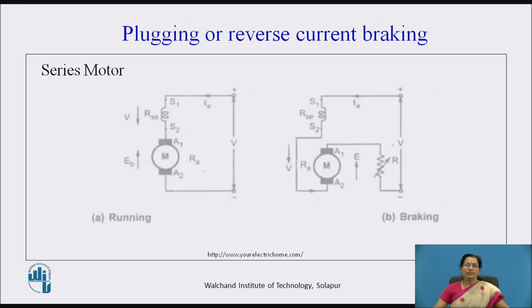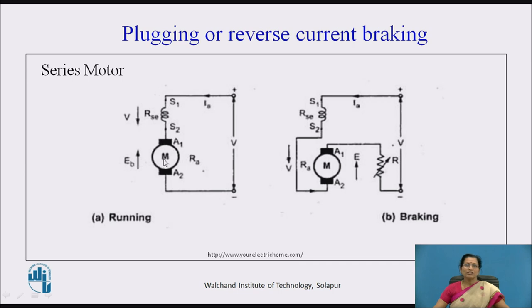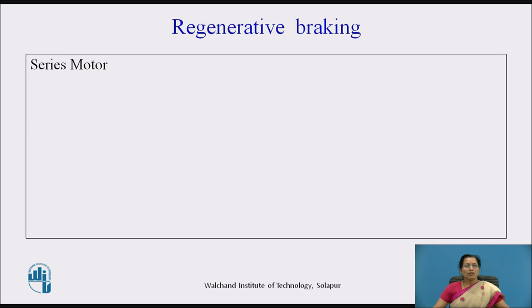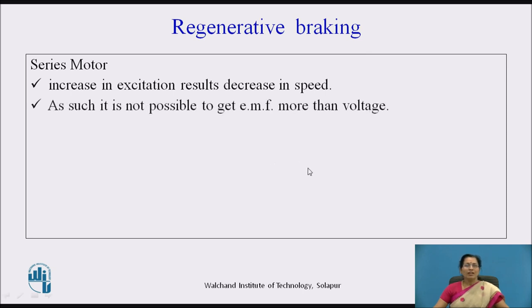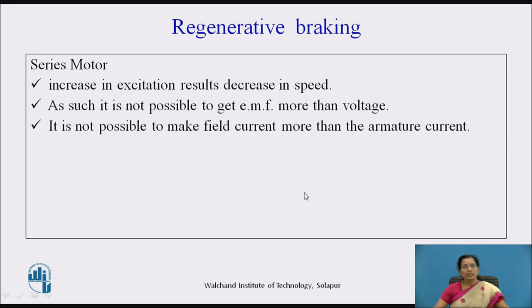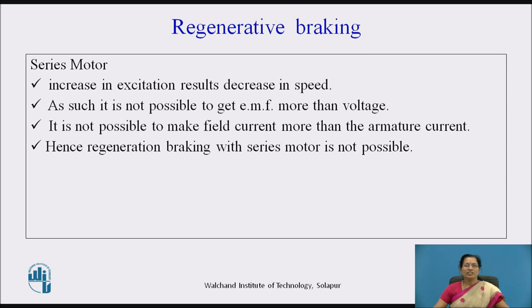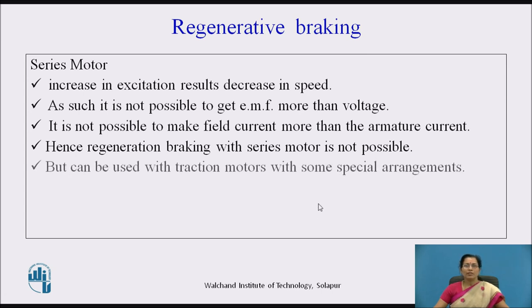For plugging or reverse current braking of a series motor, the current direction is downward, the armature connections are reversed, and a resistance is connected in series with the armature so that the opposite torque is created and braking is applied. For regenerative braking of a series motor, increasing excitation results in a decrease in speed. However, it is not possible to make the field current more than the armature current, so regenerative braking with a series motor is not possible, but can be used with traction motors with some special arrangements.